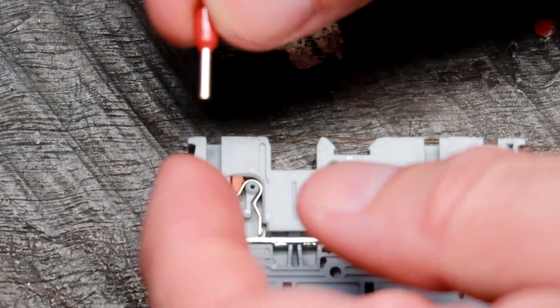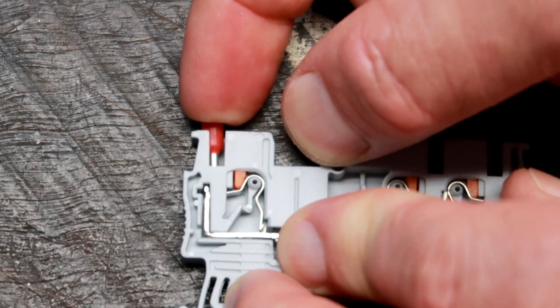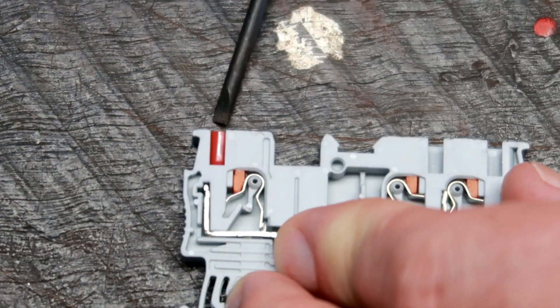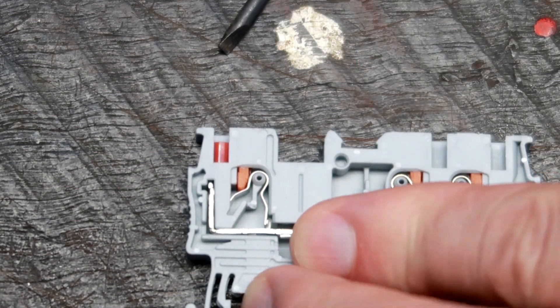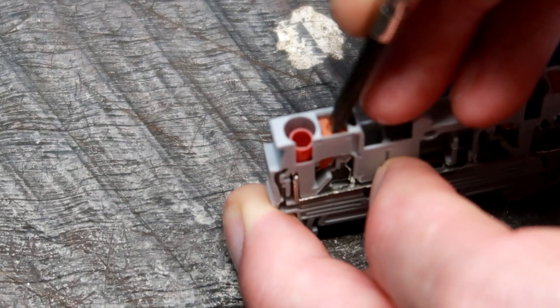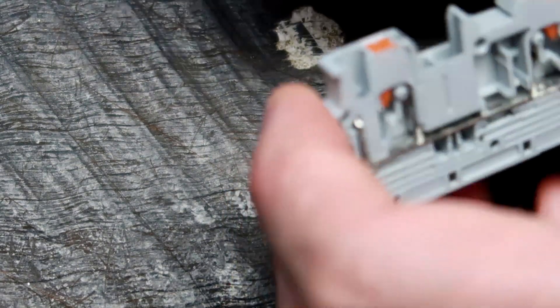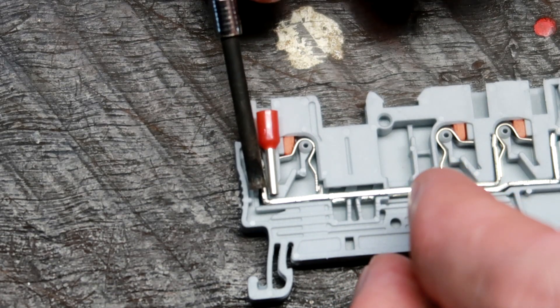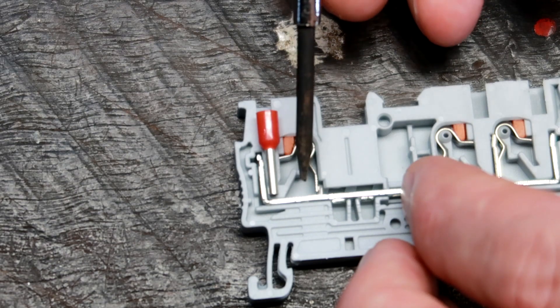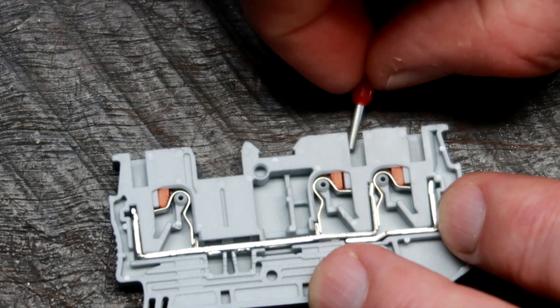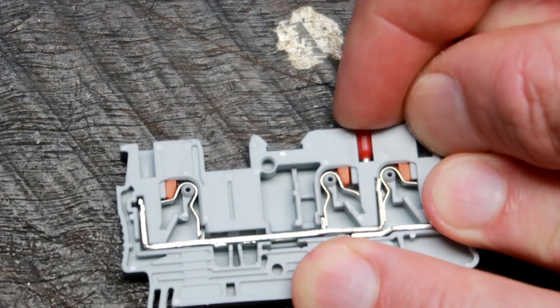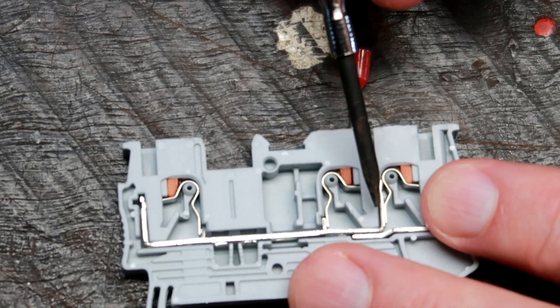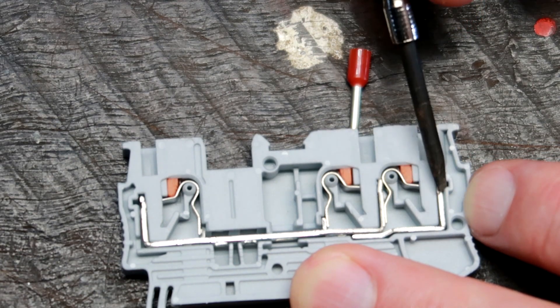So here, for example, we've got a one millimeter ferrule, and we push this into the contact, and you can see the little spring mechanism here just got pushed down by the ferrule. If I put this all the way in, that's how it looks like then. And to release it, you just press on top here of this orange button, and this will release your cable again. And we could see it goes already that far in, so the ferrule will go in all the way and the spring mechanism will push the ferrule against the bus bar on its full length. And the same is then happening here for your exits as well. So when I push this in, you can see the little spring mechanism there getting pushed down, and the ferrule will then be pushed against this bus bar here, and on this side here against this bus bar.